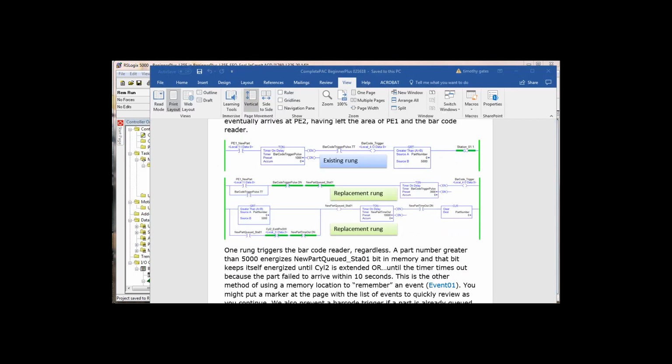In the next section of the manual, we switch over to seal-in logic from latch unlatch. So instead of setting a bit to 1 when a step is complete and then clearing it on some following step, we're going to switch over to seal-in logic where there are really no steps. It's just logic that does not require an indication of what step you're in. In other words, each rung is somewhat independent of all the other rungs.